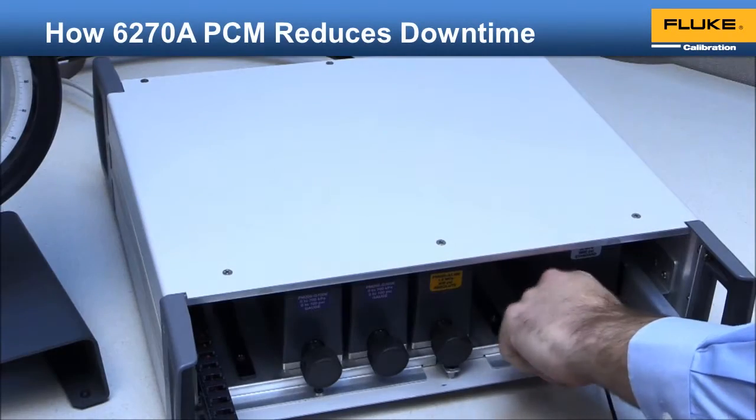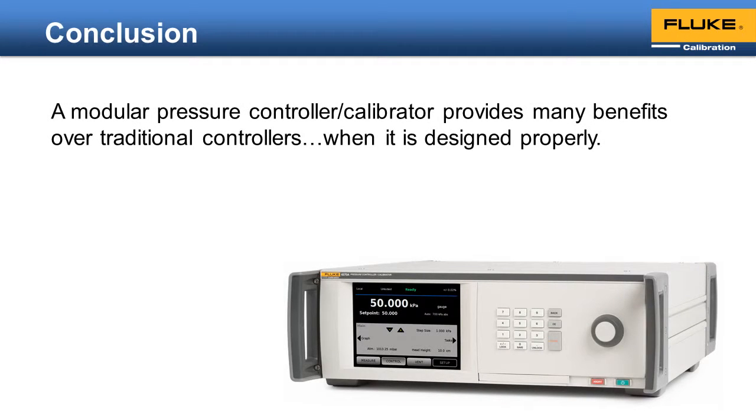Calibration of the modules is made quick and easy with the Compass for Pressure software. The control functionality in the 6270A is also encapsulated in a module. The pressure control module, or PCM, can also be easily removed and replaced through the front panel for easy troubleshooting and repair. A modular pressure controller calibrator provides many benefits over traditional controllers when it is designed properly, like the 6270A.